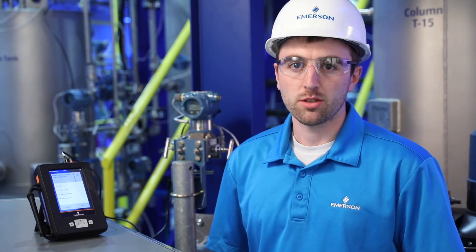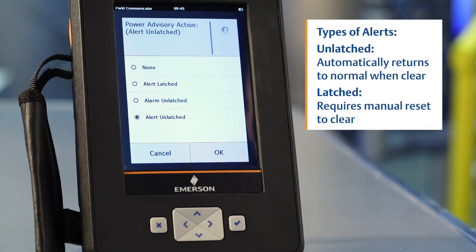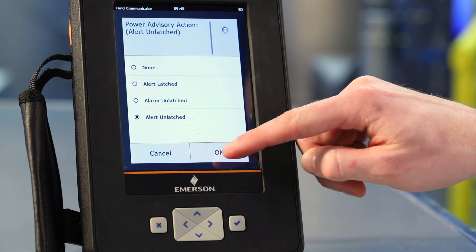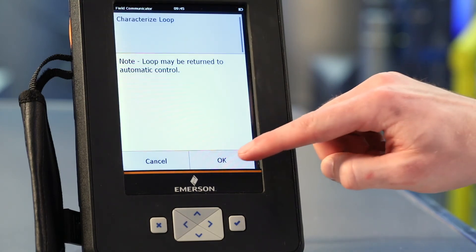Lastly, select the type of alert that you would like to see. An alert or an alarm will be generated if the terminal voltage exceeds the previously set threshold. An unlatched alert will generate a notification and clear automatically when the process returns to normal, whereas a latched alert will require a manual reset to clear. An alarm will drive the milliamp output to an alarm state. I'll be selecting Alert Unlatched and select OK. Acknowledge the automatic control message that pops up and you're done.